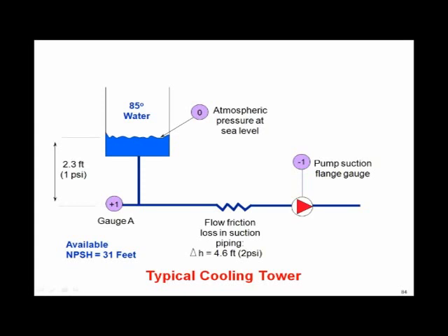So this would not be an unusual situation, would it? Does this cooling tower at Myrtle Beach have an NPSH problem? It does not. With slightly negative pressure, you may get a little air out of solution, but you remember you were pumping 85-degree water. So what would it take for 85-degree water to boil? It would take a real negative pressure, not -1 pound. It's not going to make 85-degree water boil. Probably a negative 13 or 14 pounds, that ballpark, to get 85-degree water to boil. Bottom line, the available NPSH is 31 feet. There's really nothing wrong with this application. I don't like the negative pressure, but it's not unusual. This is a typical cooling tower, no NPSH problem at all.